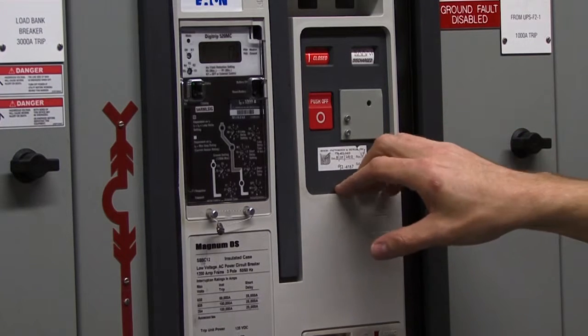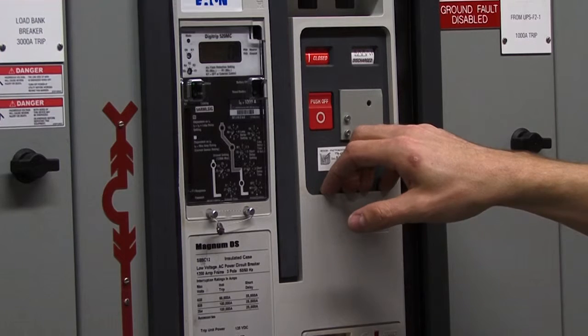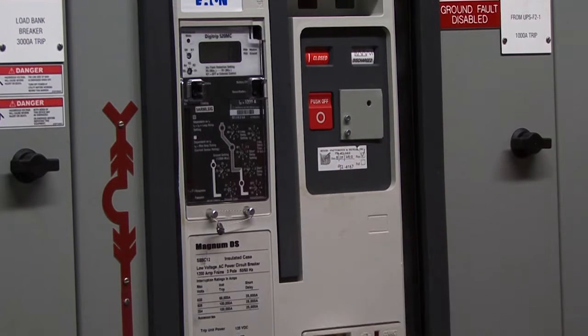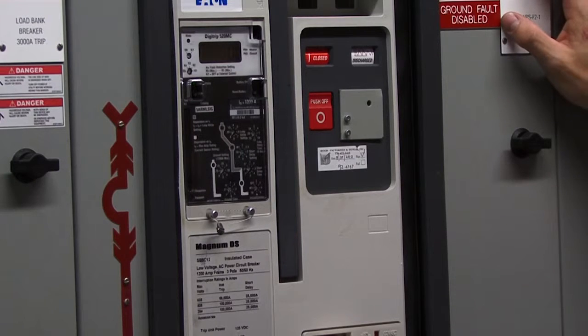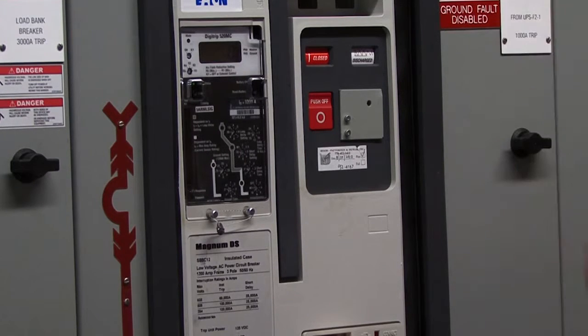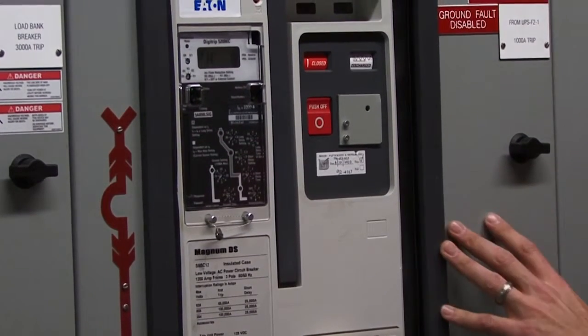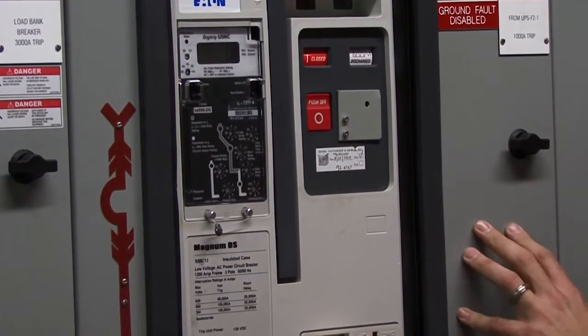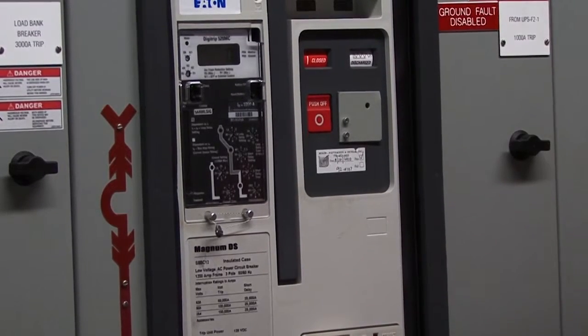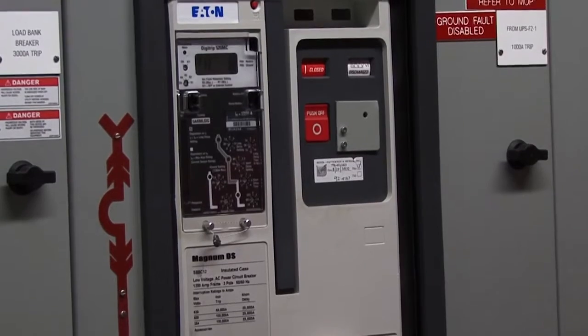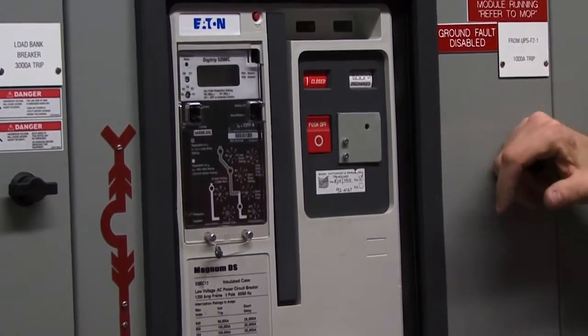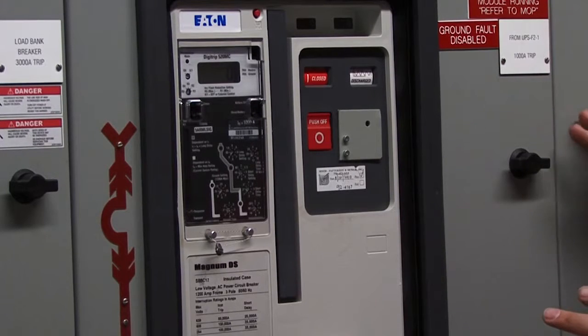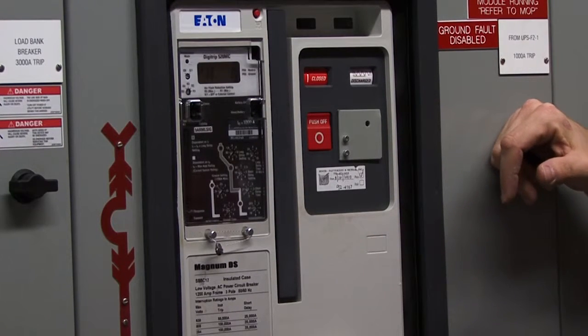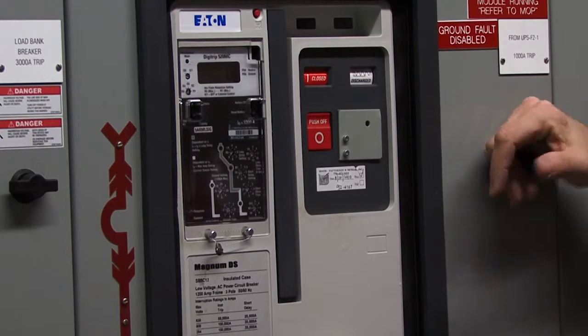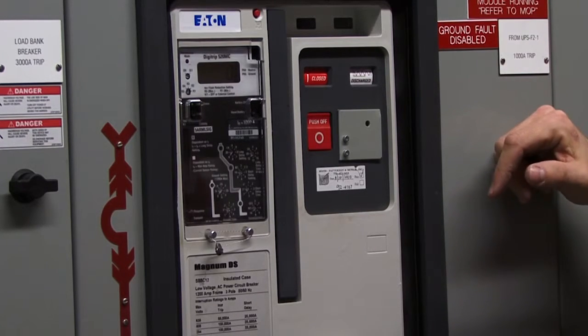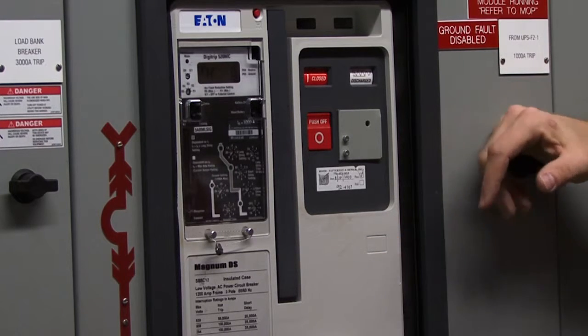So if one were to trip open, if for any reason this breaker opens on any of these modules, you should never reclose it with the associated module online and running. You want to close this breaker when the module is totally de-energized. So you close here and then you'd go and close the input breaker and start the module up. Failure to do that can cause the other modules to have a problem, and the reason for that is that closing this breaker is what tells the other UPSs that a module is part of this collective system. So if a module is running, but this breaker is not closed, the other modules disregard it.